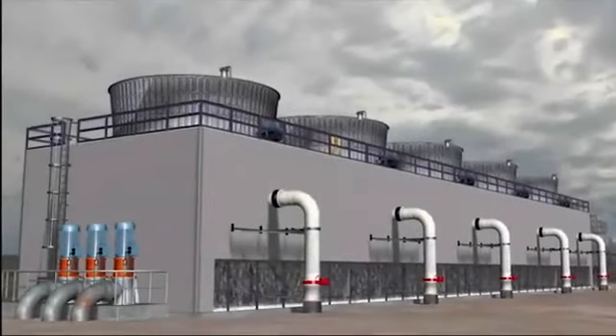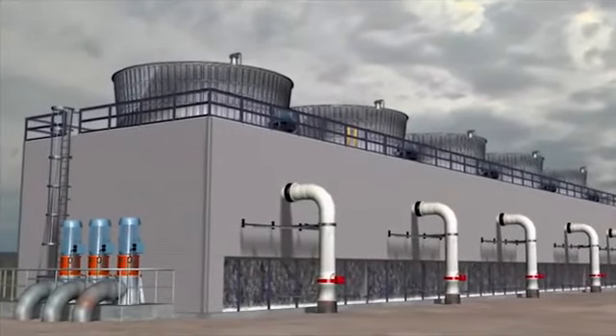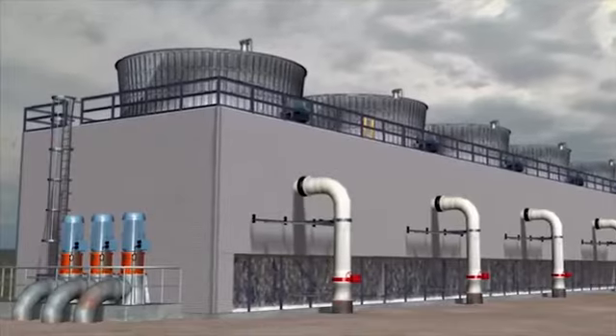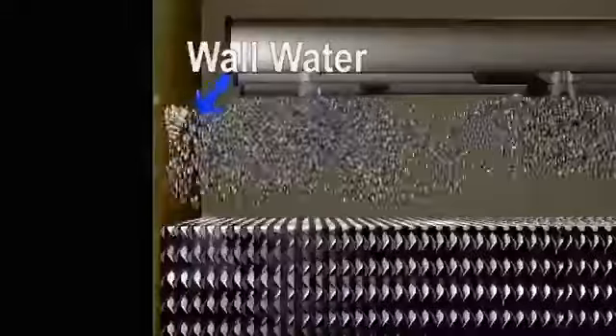Almost all of today's counterflow cooling towers have the same three problems that significantly downgrade their performance. Uneven water loading as a result of overlapping circular nozzles. Excessive wall water as a result of using circular nozzles, and inadequate water distribution systems. Almost all cooling tower nozzles spray in a round or circular pattern, and that's a problem.